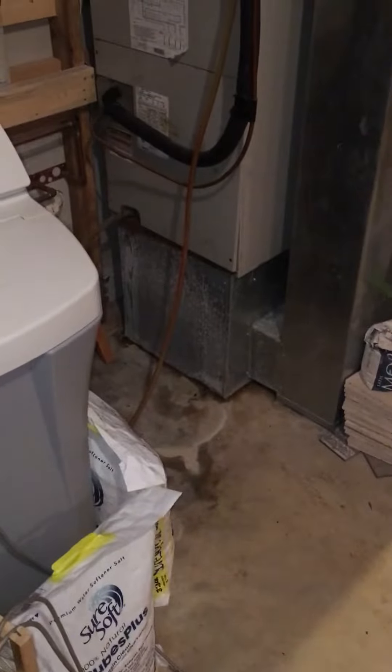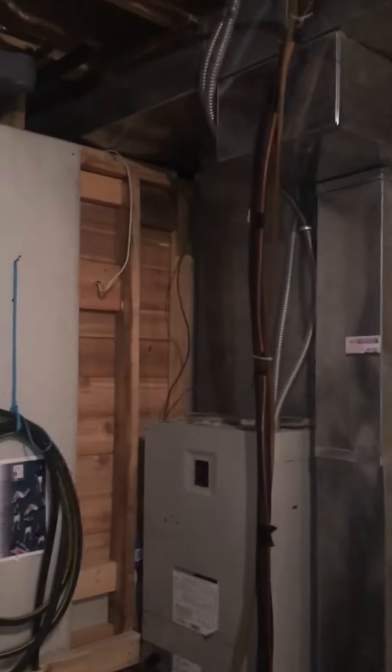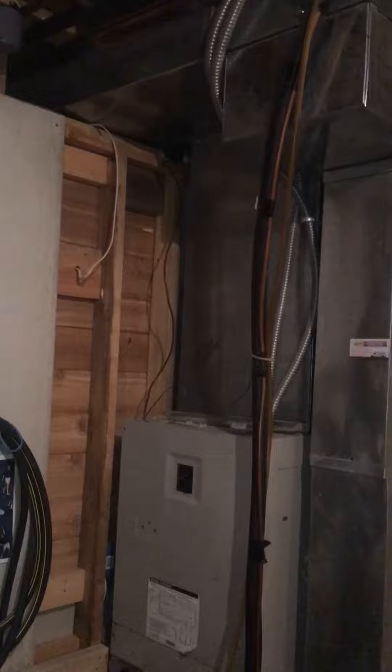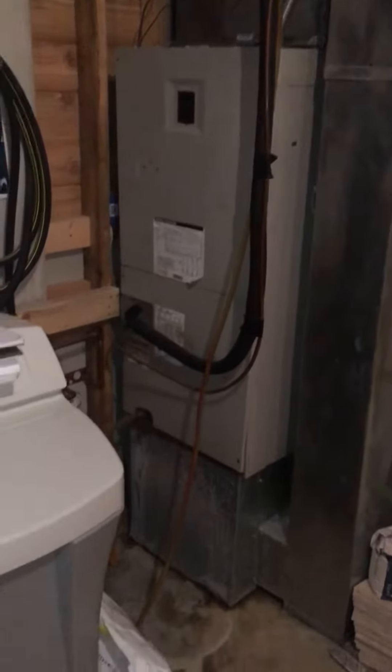We're in Debbie's basement looking at the air handler for the first floor. The return air is way too small — we need to address this situation. I've got the dimensions needed to put in a new return air drop and connect it to a new base, as you can see here. The supply duct is fine; we just need to probably shorten that when we do the new air handler and new base.